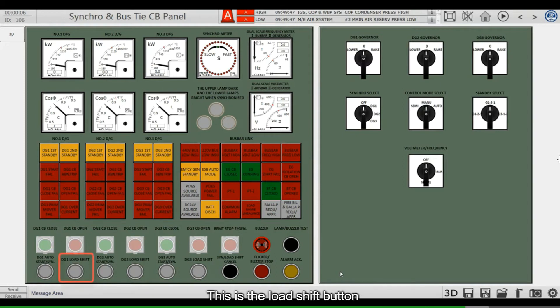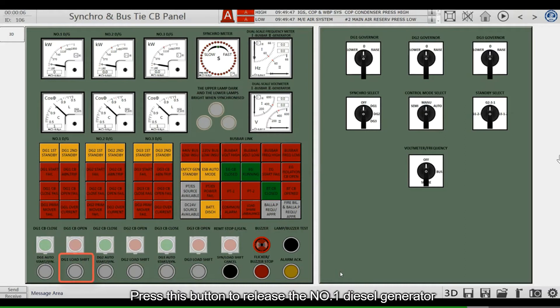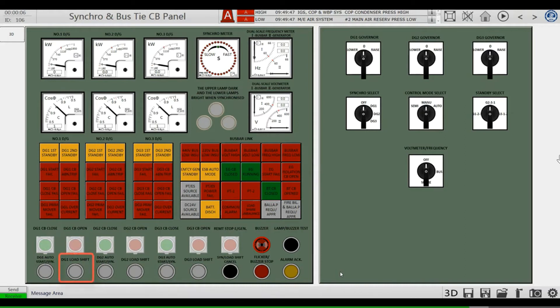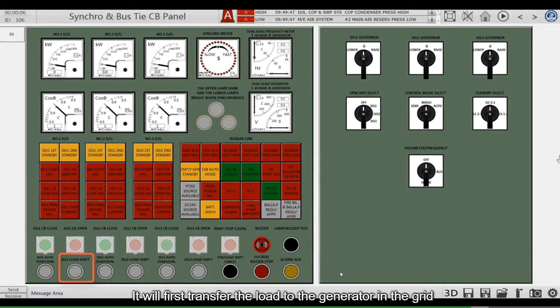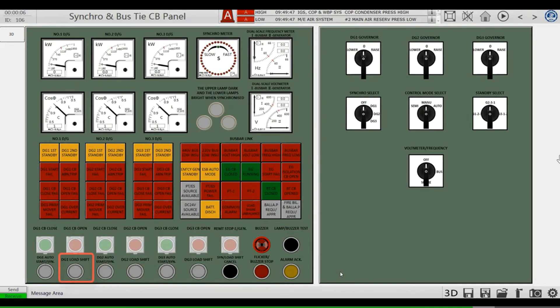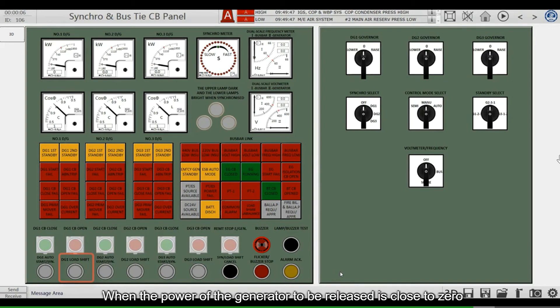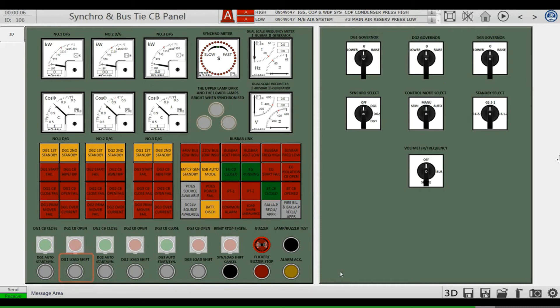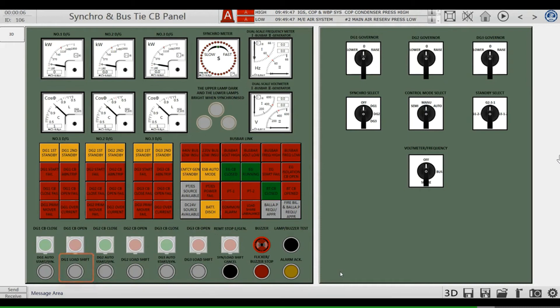This is a load shift button. Press this button to release the number one diesel generator. It will first transfer the load to the generator in the grid. When the power of the generator to be released is close to zero, it will give the open command and let the main switch open.